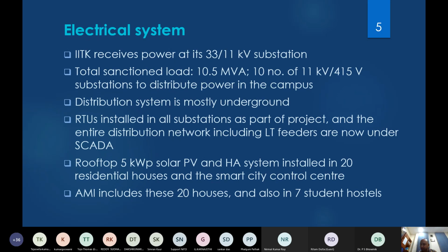About the electrical system we are dealing with: at IIT Kanpur we receive power at a 33 by 11 kV substation — that's our main substation. Then we have 10, now 11, number of 11 kV by 415 volt substations. The entire distribution system, the 11 kV network, is underground now — we have a cable distribution system. So all these substations, 11 plus 1, 12 now, have RTUs (remote terminal units) installed, and all these substations are included under SCADA now.